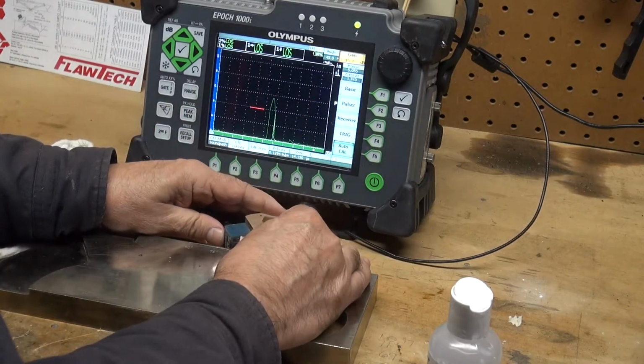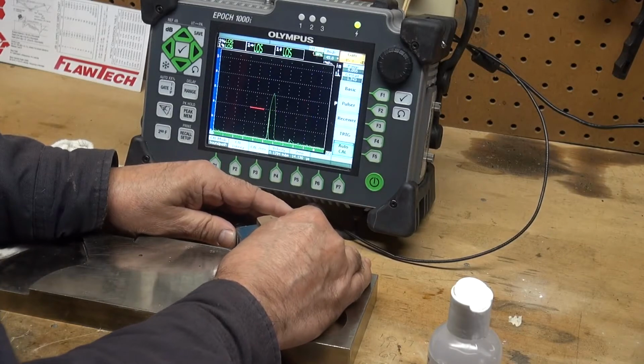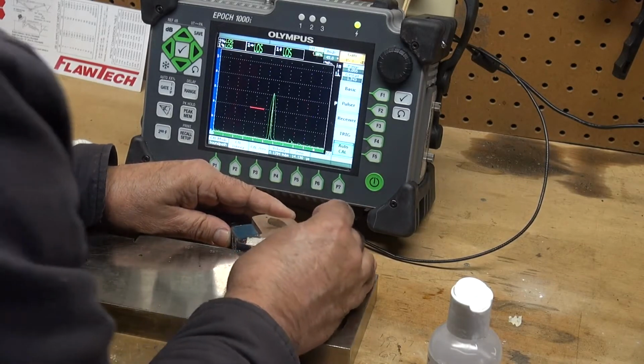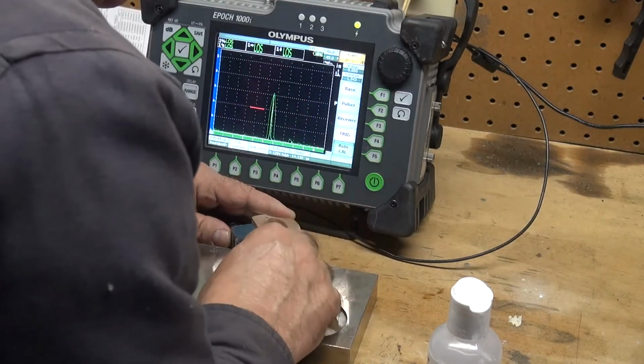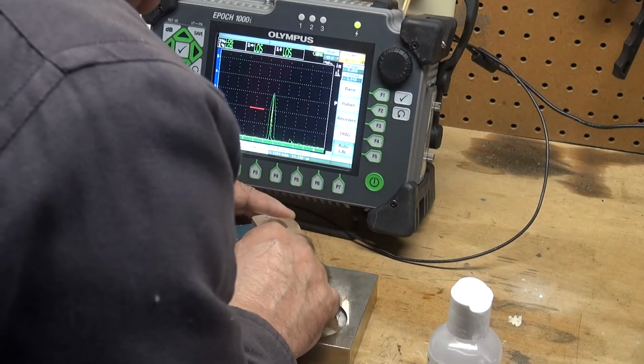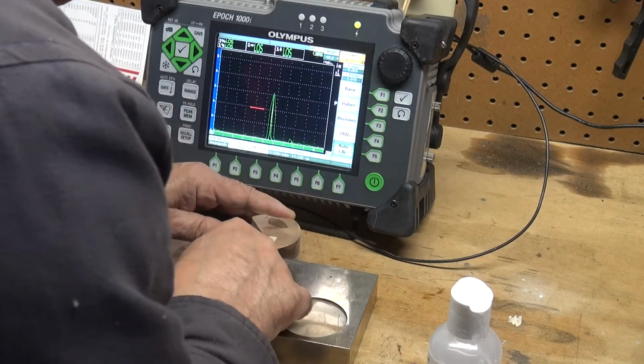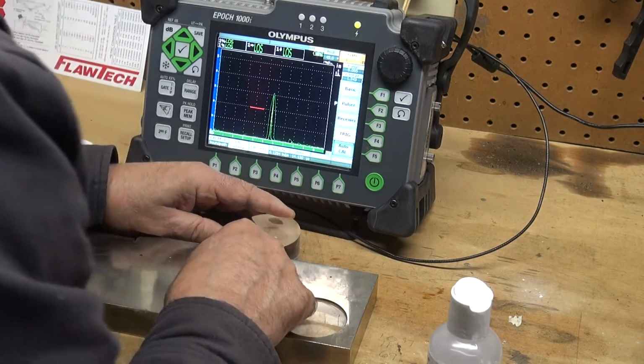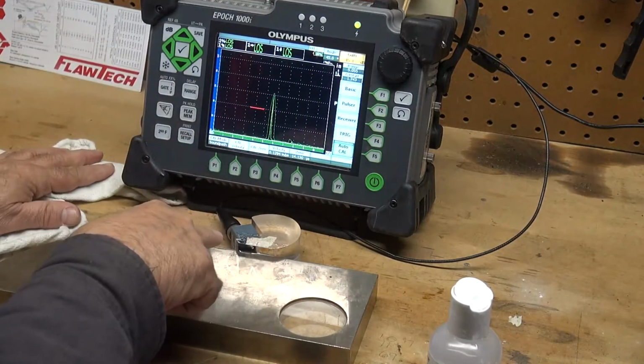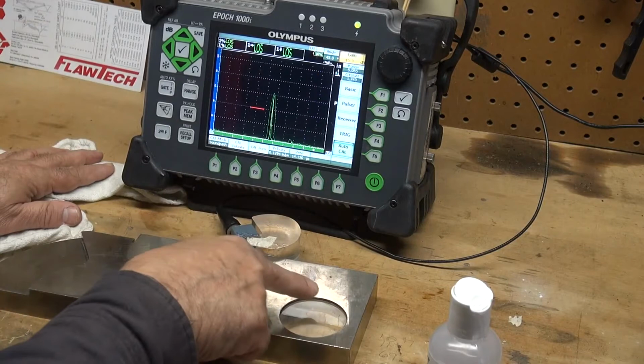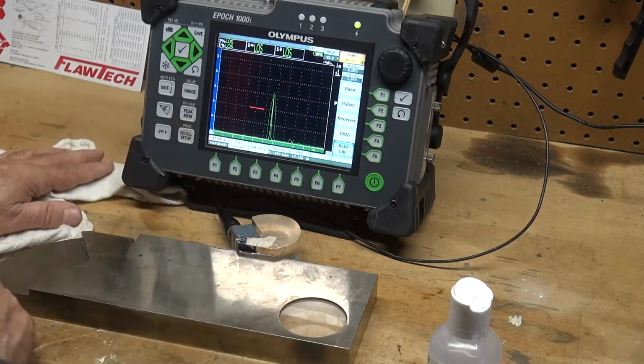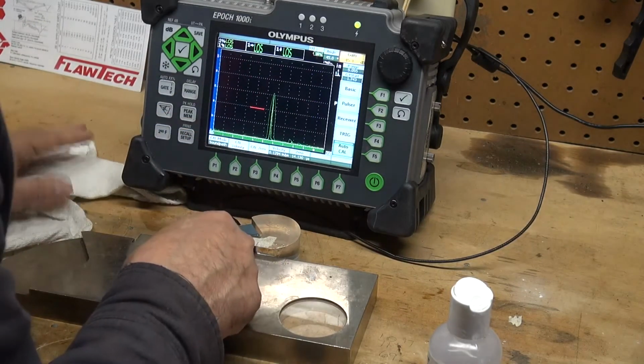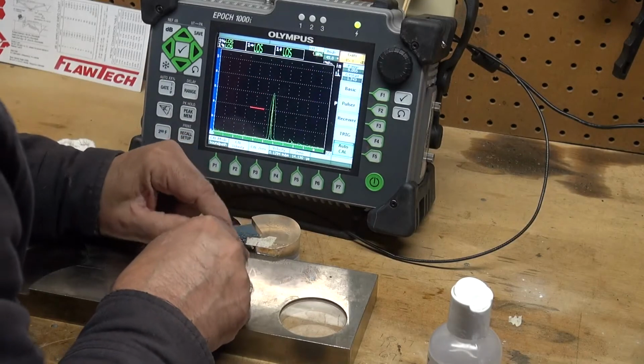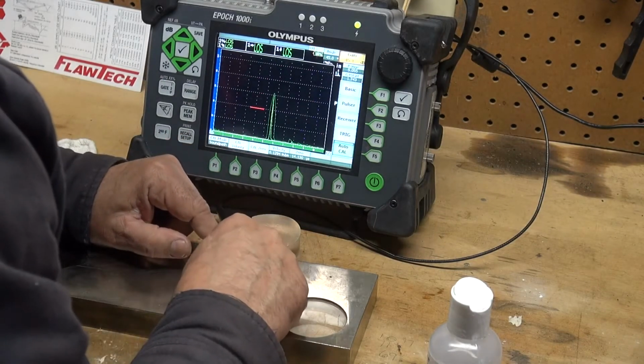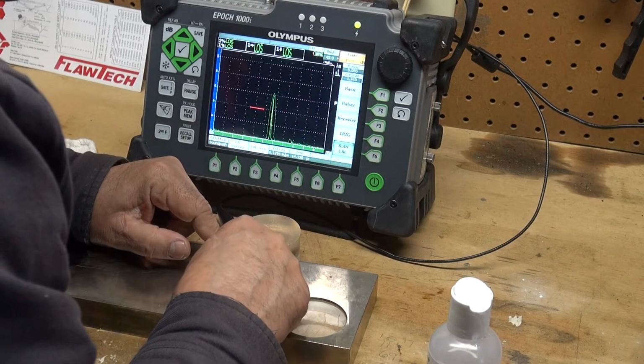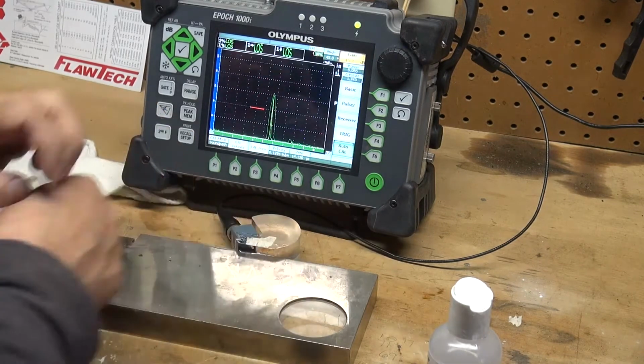and I'm going to see where that signal peaks. That signal peaks right there, and I am measuring 43 degrees. This wedge, using this hole, is coming back, and I look at my beam index point I have marked, and looking at the scale, it says 45, 44, 43 degrees.